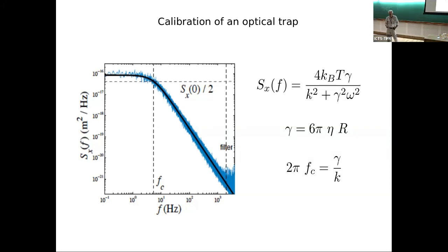In the case that you have a time-dependent spring constant, how do you calibrate the trap? This is easy, because suppose that I do it for one intensity, then I know this value. Then I can do two or three other points at different constant intensities. Usually, if you have not done bad things, the stiffness is linear in the intensity. So you know that the amount of change of the intensity corresponds to the amount of change of k.